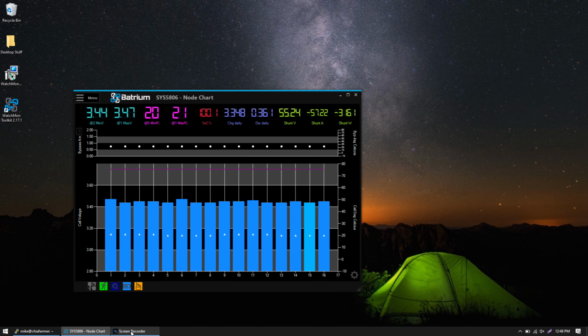With both space heaters on, we're around 57 amps or 3100 watts. You can see how quickly the voltage drops per cell on lithium iron phosphate as soon as the load's applied - there's very little stored energy around the top charge voltage. So we'll leave this running until one of the cells hits the low cutoff voltage of 2.5 volts, and see what our capacity is.